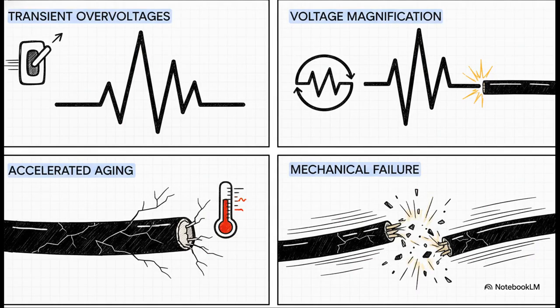So how does this actually break stuff? Well, a few ways. First, just flipping a capacitor bank on and off creates big voltage spikes, called transients. Then resonance comes along and magnifies those voltages to insane levels, high enough to literally puncture the insulation on equipment. At the same time, all those extra harmonic currents are making things run hotter and hotter. This thermally ages the insulation, making it hard and brittle over time, which just speeds up failure.